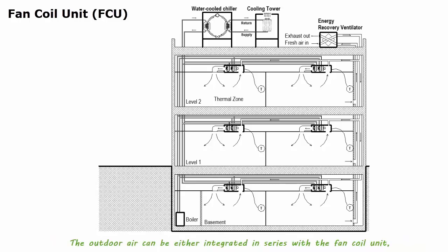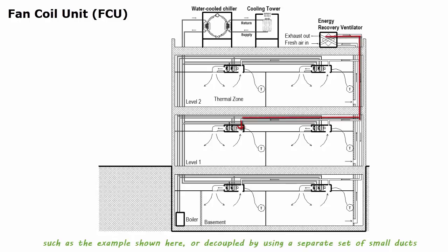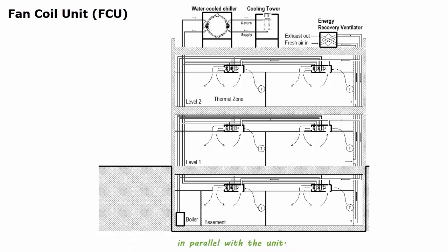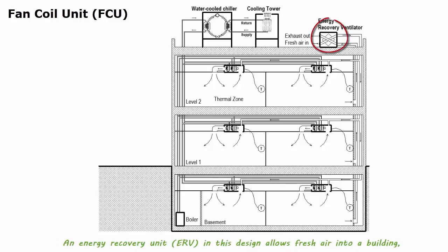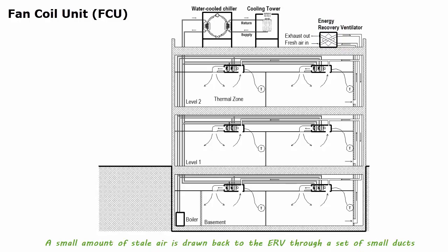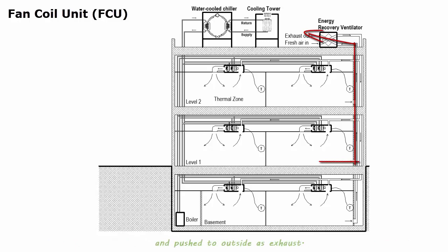The outdoor air can be either integrated in series with the fan coil unit, such as the example shown in this diagram, or decoupled by using a separate set of small ducts in parallel with the unit. An energy recovery unit, ERV, in this design allows fresh air into the building while retaining preconditioned heating or cooling by a heat exchanger. A small amount of stale air is drawn back to the ERV through a set of small ducts and pushed to outside as exhaust.